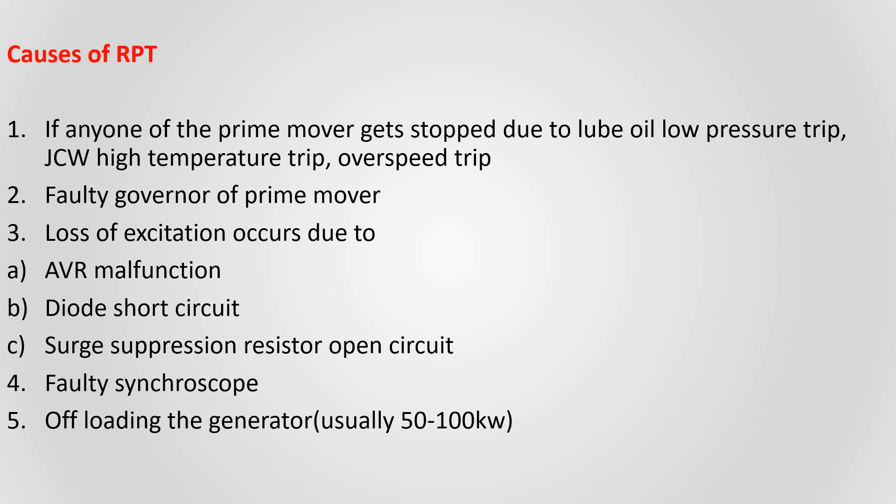If any one of the prime movers gets stopped due to lube oil low pressure trip, jacket cooling water high temperature trip, or overspeed trip — these are the main trips for the safety of the prime mover. If any one of these trips happens, the governor has to cut off the fuel supply to the prime mover, then the prime mover gets stopped, and then reverse power flow will occur. A faulty governor of the prime mover can also cause this.